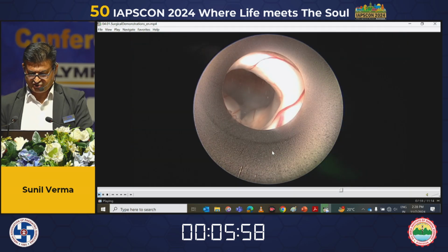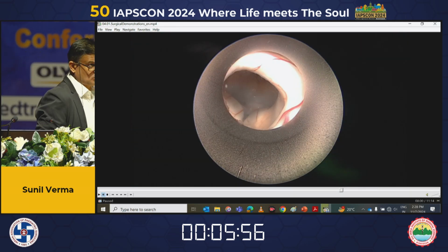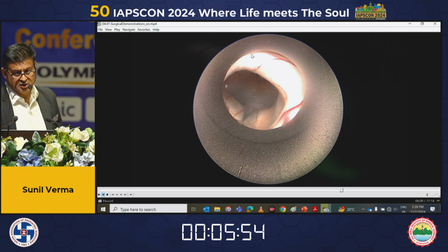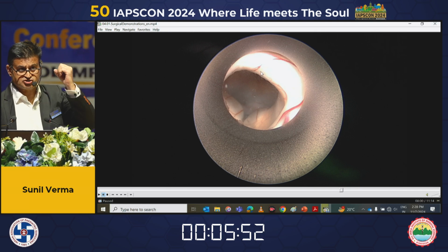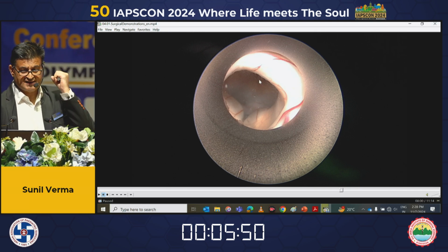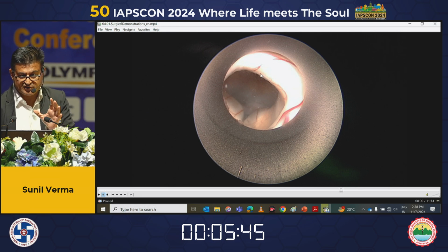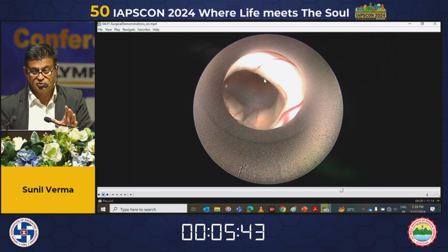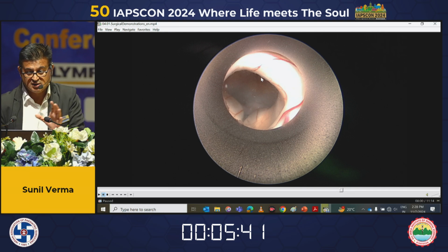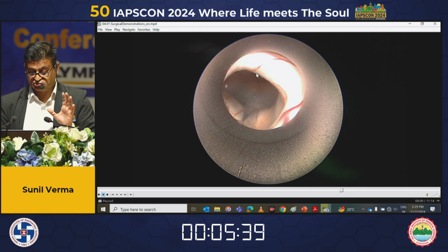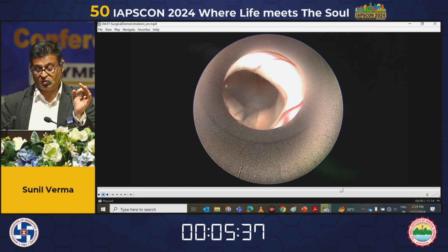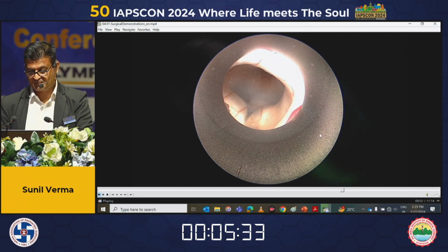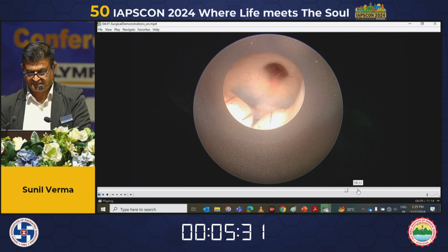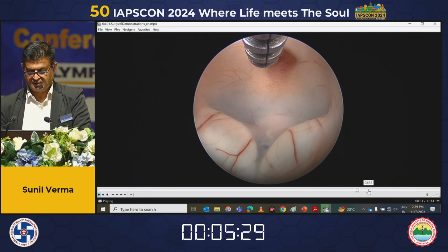Now there is a very special and important luer lock. In case you are not sure whether you can pass through the foramen of Monro, you can open the luer lock, push this scope inside the endoscopic sheath, and then travel together and check whether you can pass through the foramen of Monro or not, or whether it is going to cut the edges of the fornix. So this is a very good luer lock which they have given, and you can check whether the endoscope can pass or not. Retracted into the endoscope sheath, veins in the area of the foramen of Monro.